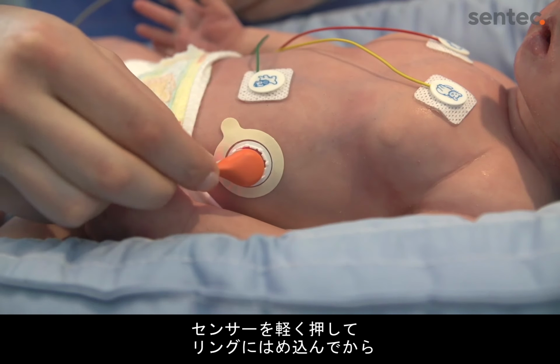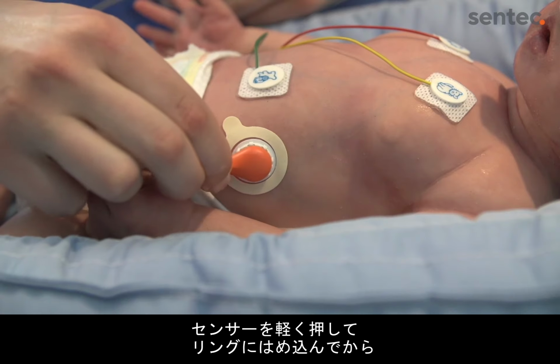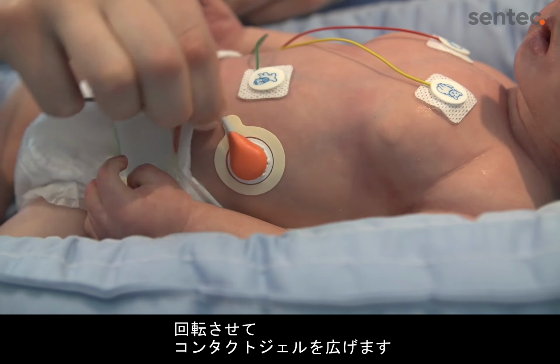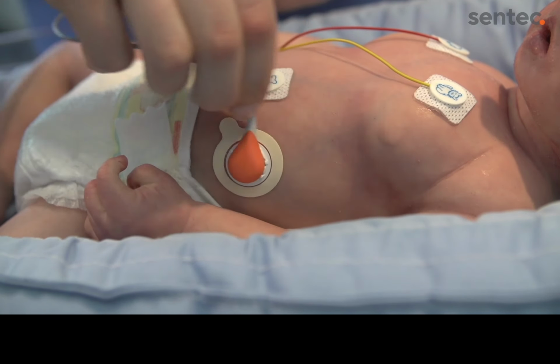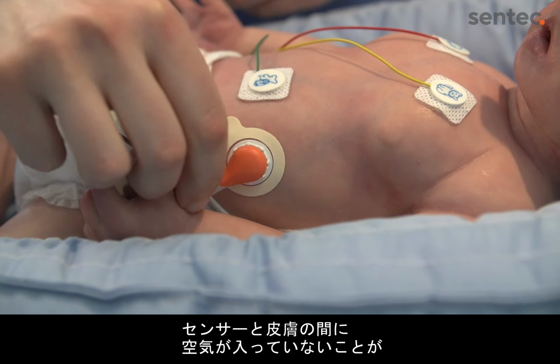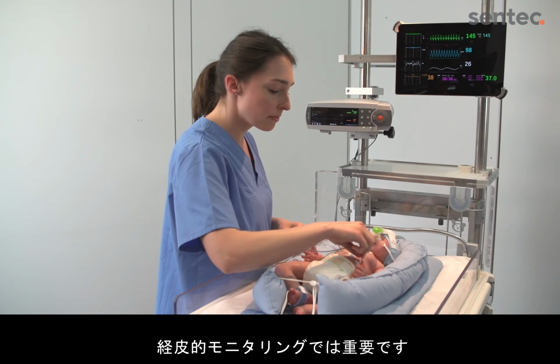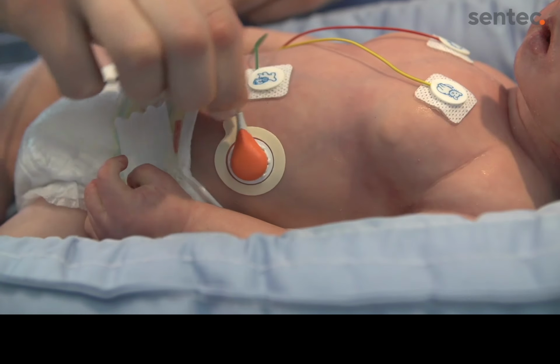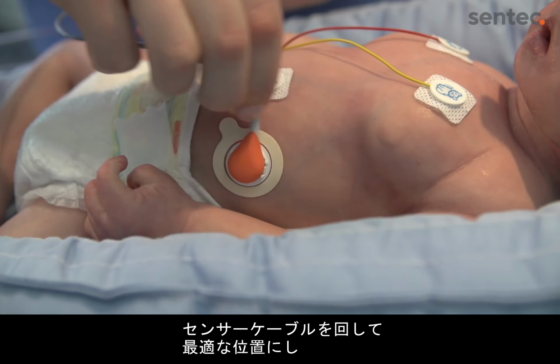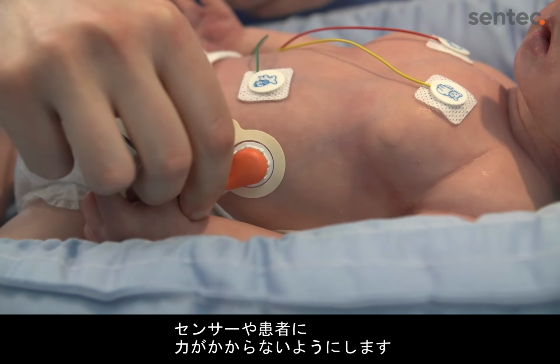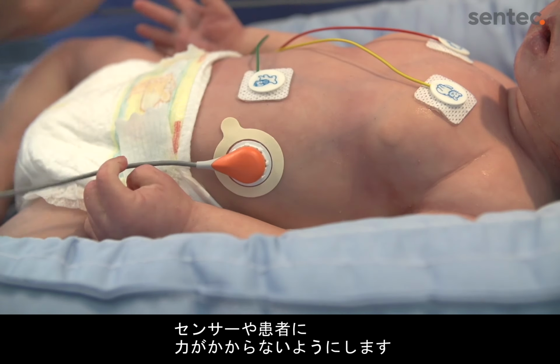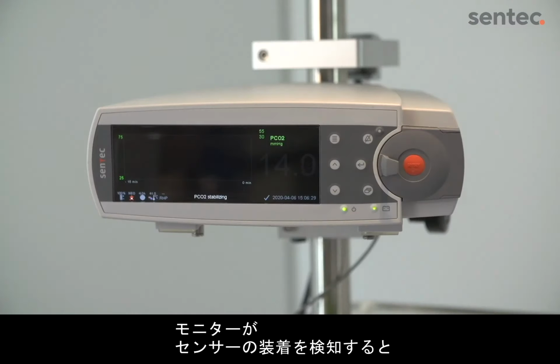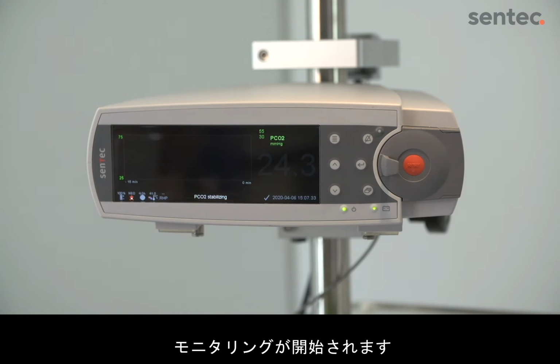Then, apply slight downward pressure to clip the sensor into the ring. Rotate the sensor to distribute the contact liquid. A good airtight seal between the sensor and the skin is essential for transcutaneous monitoring. Rotate the sensor cable into the best position, avoiding any strain on the sensor or pressure on the patient. Once the monitor detects that the sensor is on the patient, the device will initiate monitoring.